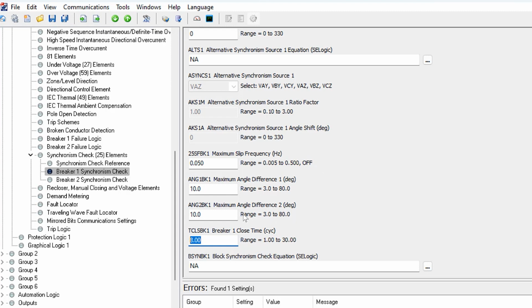And then lastly, we have the maximum angle differences, angle 1 and angle 2. Typically, we would set the setting ANG1BK1, this one over here, for sync check and auto reclosing the circuit breaker. So for automatic closing of the breaker. And we would set the ANG2BK1 setting for when we're manually closing the breaker. And typically you would allow a higher phase angle difference when closing the breaker manually than when issuing an automatic closing signal. So we could, for example, set our angle 1 to 20 degrees and our angle 2 to 30 degrees. All right, so we have programmed all the settings for the sync check function.